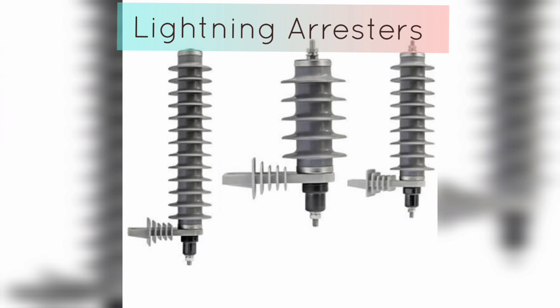There are several types of lightning arrestors: silicon carbide arrestors (SiC), which use silicon carbide as the nonlinear resistor and are typically used in medium and high voltage systems; metal oxide arrestors (MOA), which use a metal oxide varistor (MOV) as the nonlinear resistor and are commonly used in low, medium, and high voltage systems; and gas discharge tube arrestors (GDT), which use a gas-filled tube and are commonly used in low voltage systems. Proper installation and maintenance of lightning arrestors are essential for ensuring the safe and reliable operation of electrical equipment and systems.